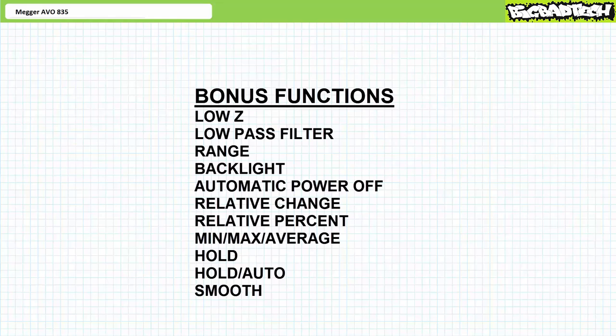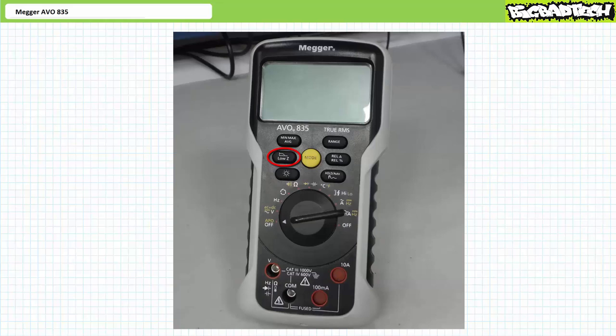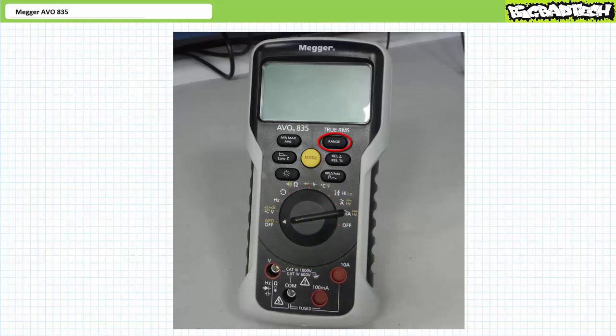We've already examined the low Z and low pass filter function buttons in the voltmeters lecture, available at the Big Bad Tech Channel. The low Z button drops the impedance of the AVO 835 in voltmeter mode, allowing measurement for systems with ghost voltages. Another press of this button enables a low pass filter that blocks frequencies above 800 hertz. We've also already examined the range button — the Megger AVO 835 is ordinarily auto-ranging for most functions, meaning the meter itself chooses the most appropriate range for the present measurement. If you want to manually range the meter, you can force it into a specific higher or lower range with the range button.